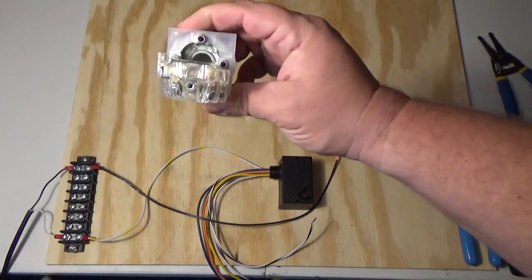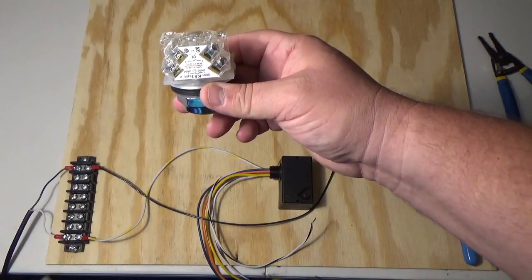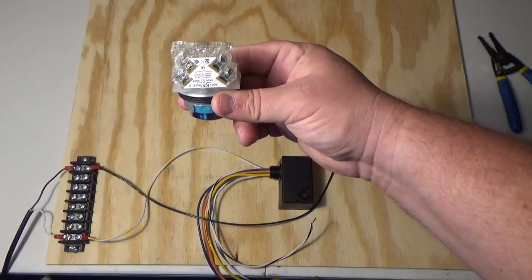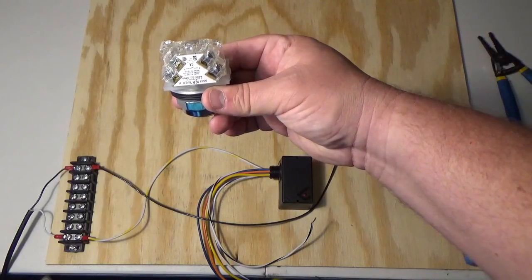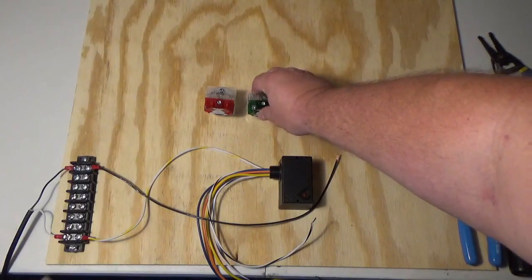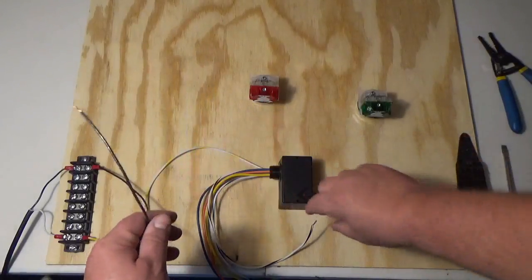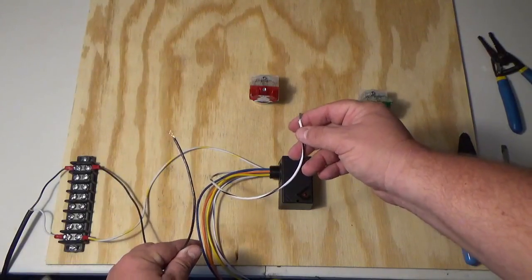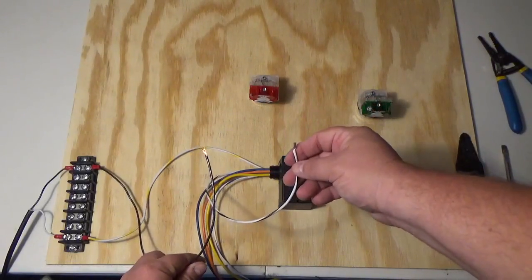I also have another push button that's clear. This style happens to be clear, sometimes they come in black. You have two sets of contacts, so this is a combination normally open and normally closed. When we push the button, it's in a normally closed state, but as soon as I push the button it opens and then we make contact and it closes the other. I have 120 volts here and my other end of my coil is here. I'm going to connect these two wires to a normally closed switch so you can see what happens.